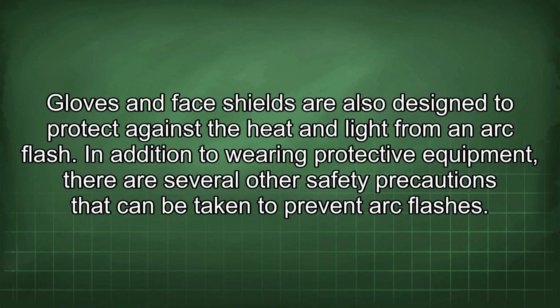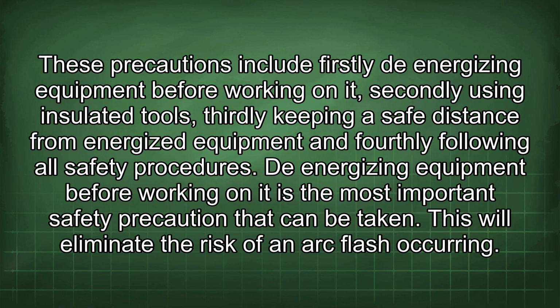In addition to wearing protective equipment, there are several other safety precautions that can be taken to prevent arc flashes. These precautions include firstly de-energizing equipment before working on it, secondly using insulated tools, thirdly keeping a safe distance from energized equipment, and fourthly following all safety procedures. De-energizing equipment before working on it is the most important safety precaution that can be taken. This will eliminate the risk of an arc flash occurring.